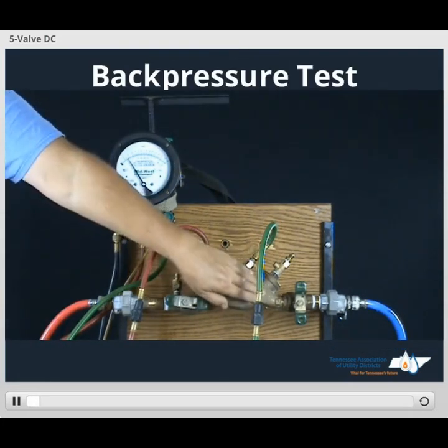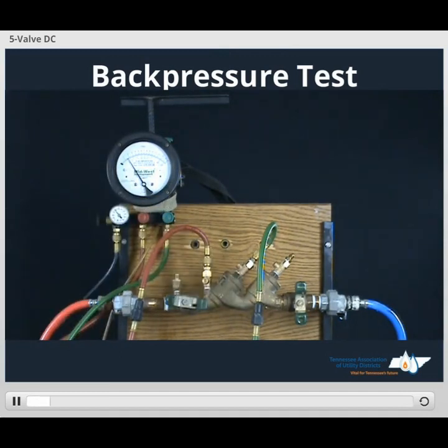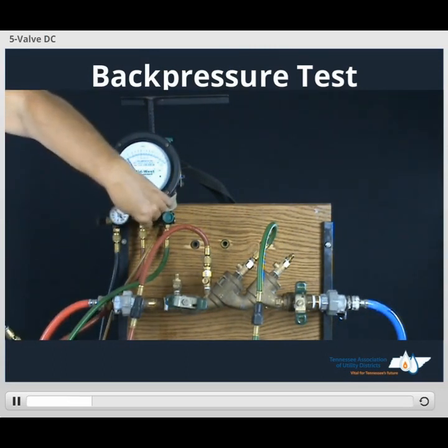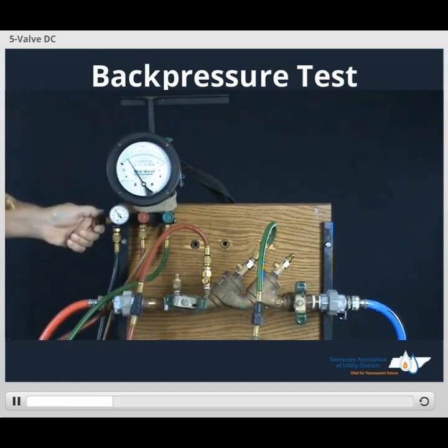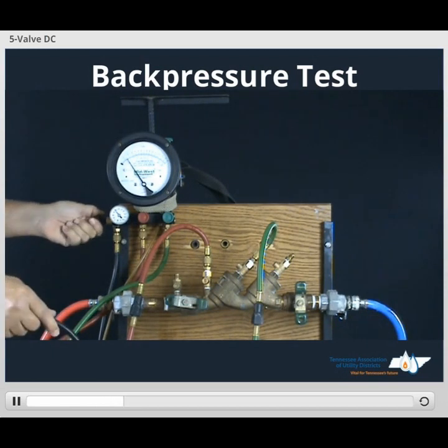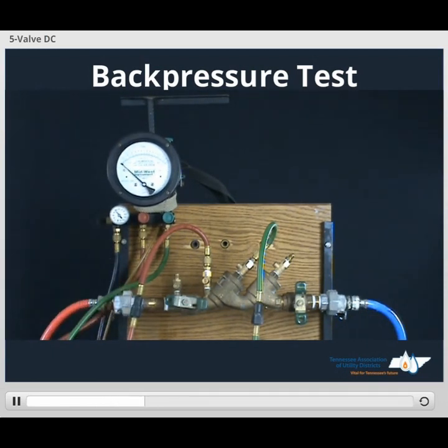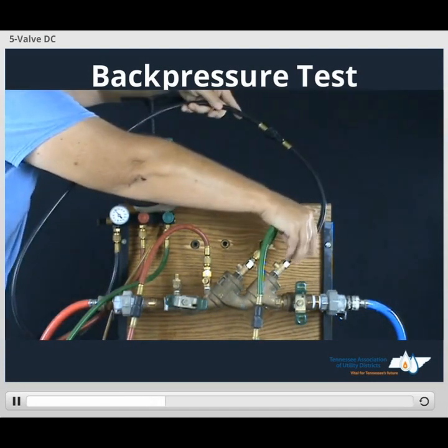In order to test our number 2 check valve against back pressure, we'll take our bypass hose. We want to purge the line before we hook it up, so we'll open up our high side valve — one turn's plenty. We'll take our bypass valve, open it up, purge the line, close bypass valve. Then we'll take our bypass hose, connect to test cock number 4.